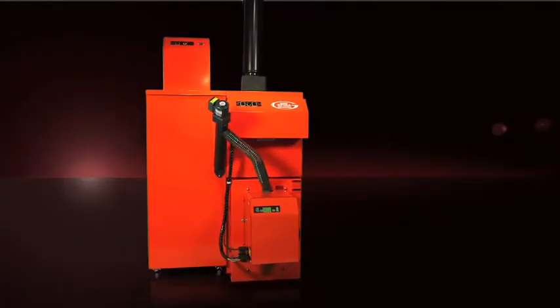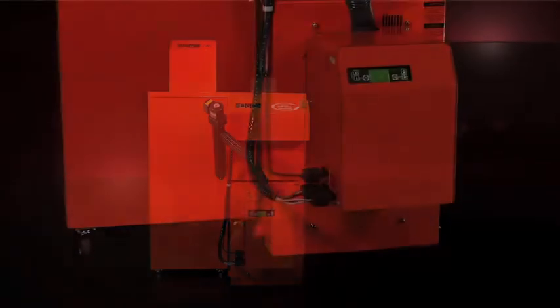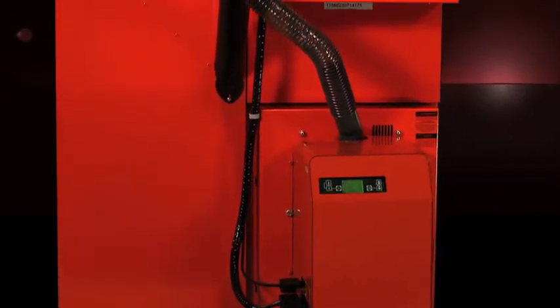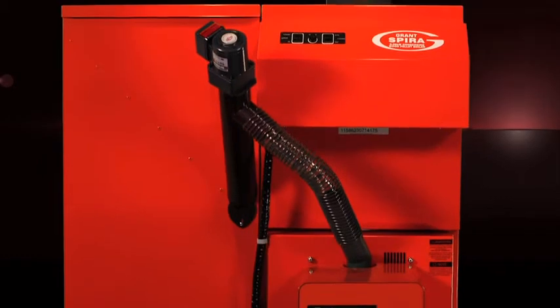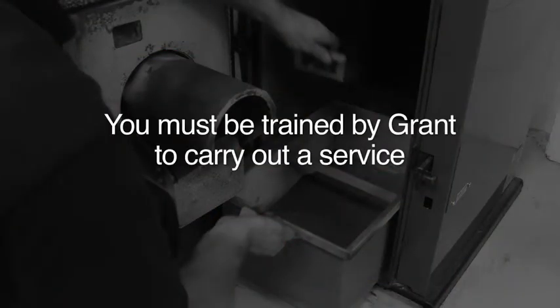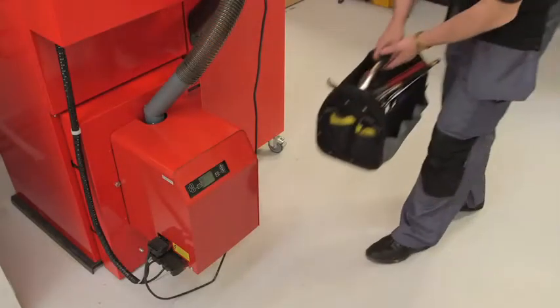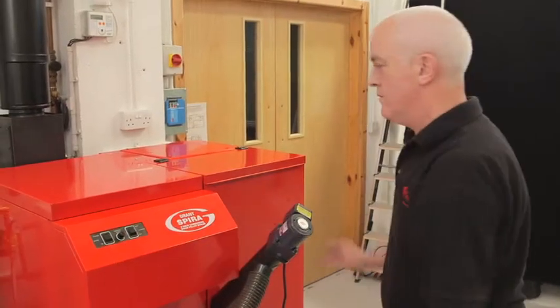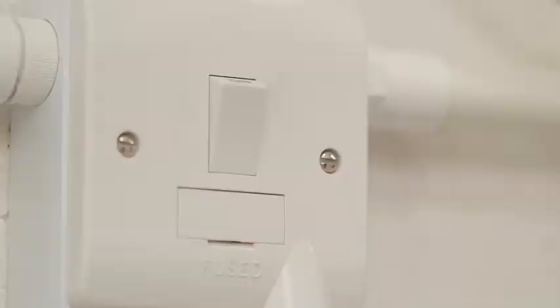The Grant Spira biomass boiler will need a full service after 12 months of operation, or when the burner display screen shows that it's due, whichever comes first. You can only carry out the service if you've been trained by Grant. First, you need to check that the boiler switch is set to standby. If it is running, wait for the boiler to stop, then isolate the electrical supply to the boiler.